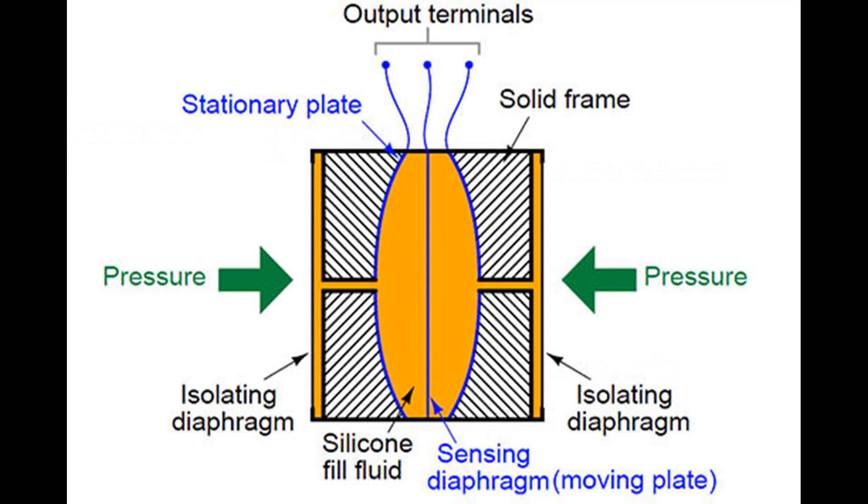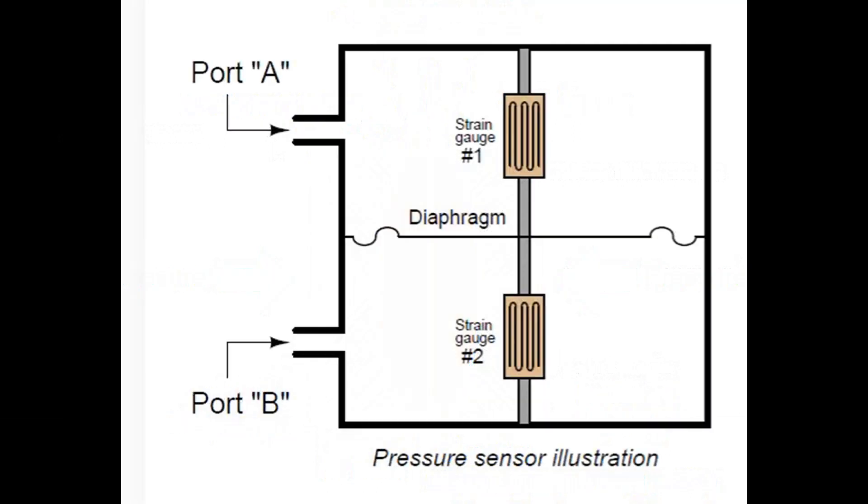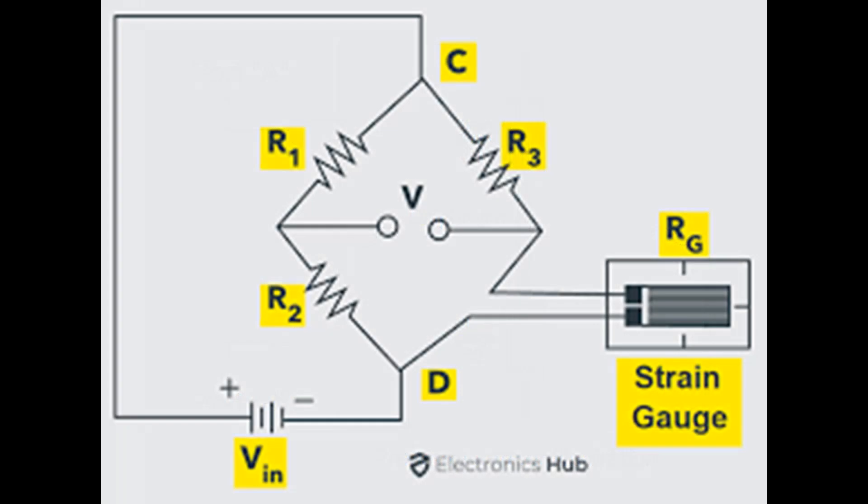It consists of a diaphragm or membrane exposed to the fluid pressure. As the fluid pressure changes, it causes the diaphragm to deform. Many modern pressure sensors use strain gauges attached to the diaphragm. When the diaphragm deforms due to pressure, the strain gauges undergo mechanical deformation, changing their electrical resistance. The change in resistance is proportional to the applied pressure.